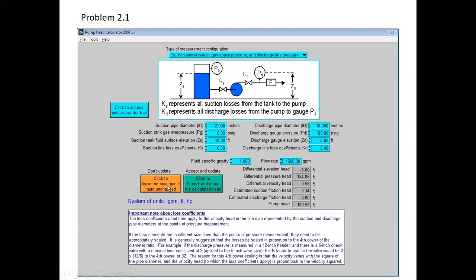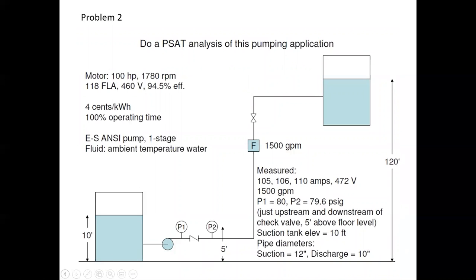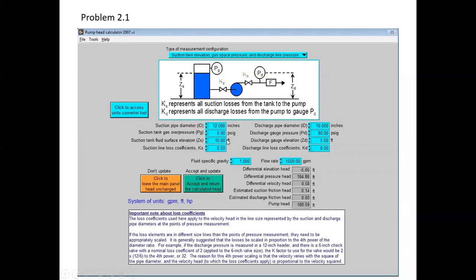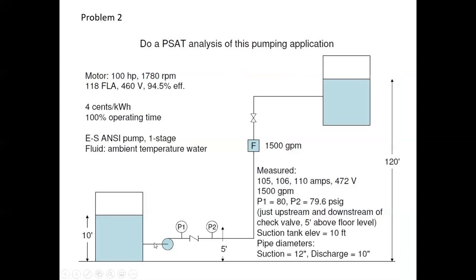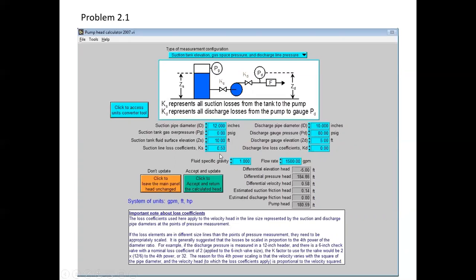Let's see. So we just plug everything into the diagram that shows the suction tank. So 12-inch pipe on the suction, 10 on the discharge. I think we had, yeah, we had 80 PSI on the discharge, 0 up here. That's the gas overpressure. We don't have any. 10 feet on the elevation here and 5 feet on the gauge. And for the discharge coefficient, it's the sharp-edged entrance on this side, and there's nothing between the pump discharge flange and the pressure gauge. So we don't have any loss in there, nothing significant enough to include. Specific gravity 1, and our flow rate is 1500 GPM.